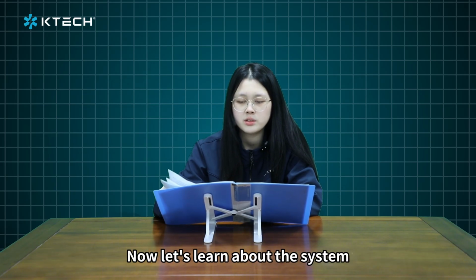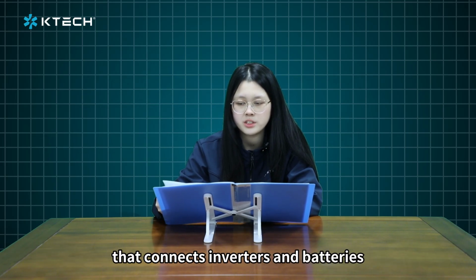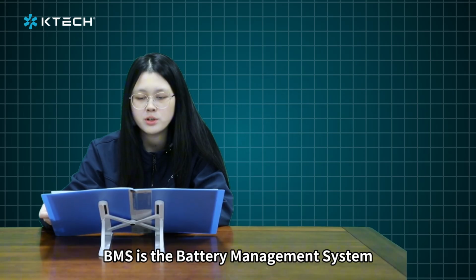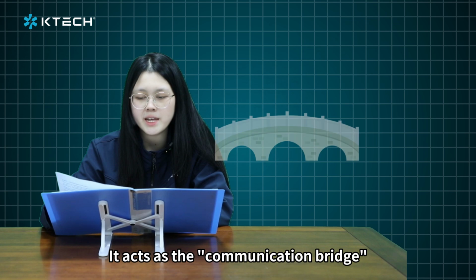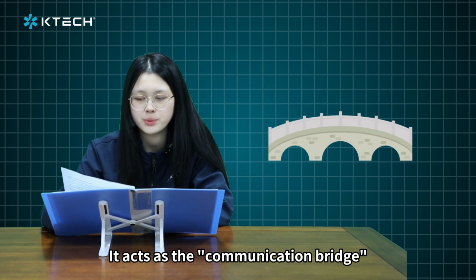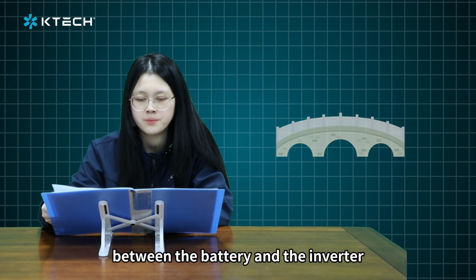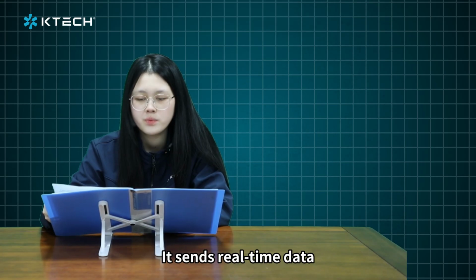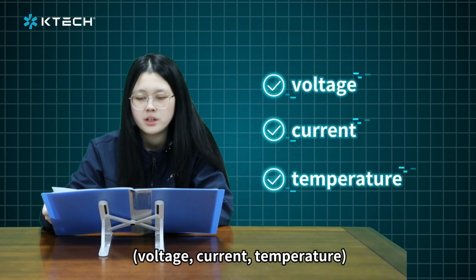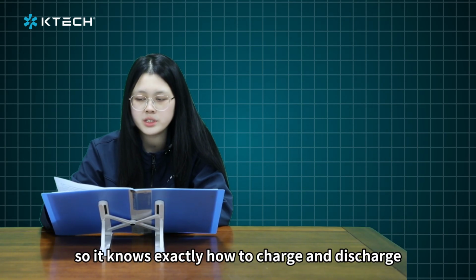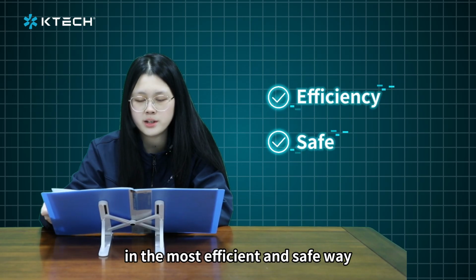Now let's learn about the system that connects inverters and batteries. BMS is the battery management system. It acts as the communication bridge between the battery and the inverter. It sends real-time data like voltage, current, and temperature to the inverter so it knows exactly how to charge and discharge in the most efficient and safe way.